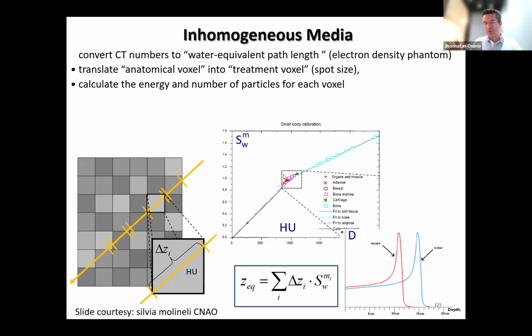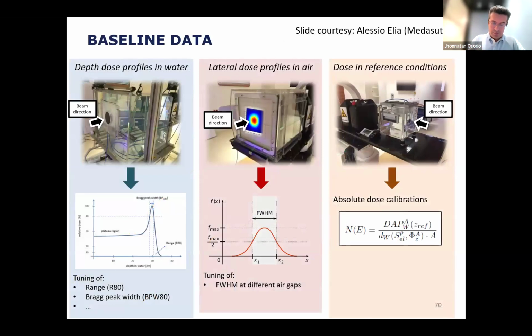And that's the trick. The conversion table or graph is basically this. Here on the x-axis, you have the Hounsfield unit, and here you have the stopping power relative to water. Basically, you need to have the information for each level of gray, how many particles are released in that medium, and how much energy is given by the stopping power, assuming that this gray level is like a density of the medium. So it's a trick that we found in order to be able to make the plans, basically. Then once you overcome this problem, the question is, okay, which kind of data do I need to provide to my TPS in order to make the acceptance and the commissioning of my TPS?